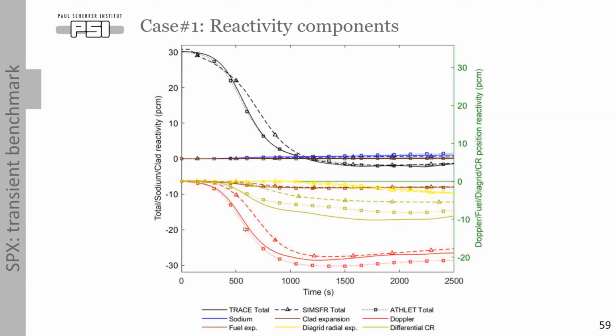But the bottom group is for the right axis, and here we see negative Doppler because fuel temperature goes up, but also we see negative differential control rod. This is because we have a slight increase of outlet coolant temperature, and this results in heating up of control rod drive lines and slight injection of control rods in the core. This is a very delicate effect to predict also.